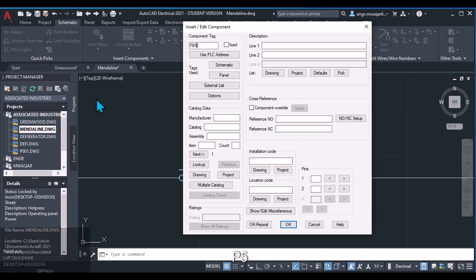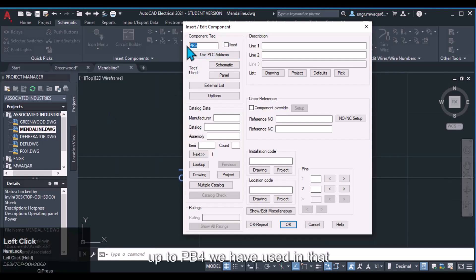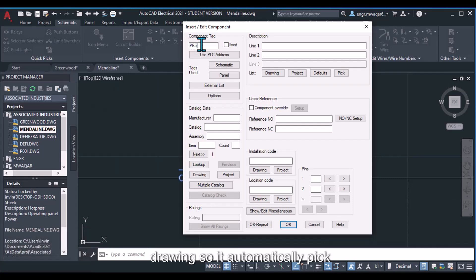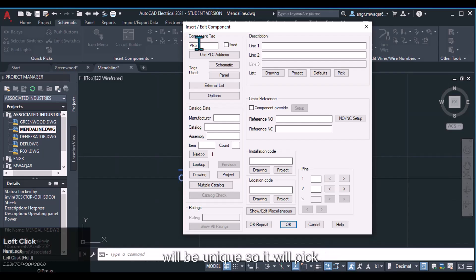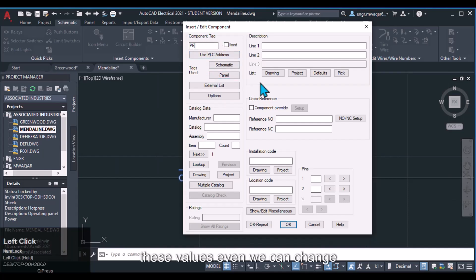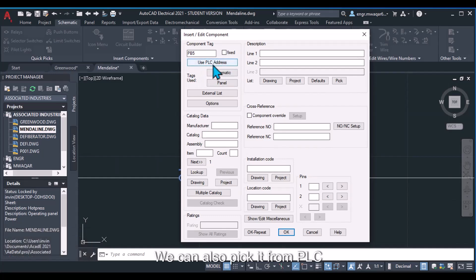We have another drawing in which some circuits were already created, using tags PB1 through PB4. So AutoCAD Electrical automatically picks PB5 as the next available tag. In a project with multiple drawings, component tags must be unique across all drawings — the software tracks this automatically. We can also change these tag values manually, and we can pick addresses from a PLC panel if needed.